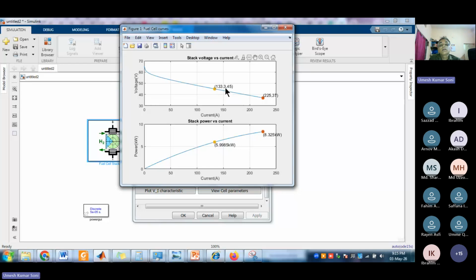So we have 133.45, 133.3, and 45 volt. What is the multiplication of that? This is the power—power is 5.998, that is 6 kilowatt. This is the nominal value, but for maximum values of everything, we have 8.325 kilowatt. So this is the nominal value, and we always have to target the nominal value, because we have to operate the fuel cells at nominal values. This is power versus current.